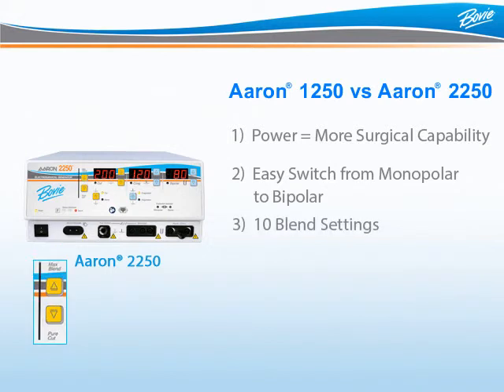Third, the Aaron 2250 offers 10 blend settings so the surgeon can find his perfect blend of cut and hemostasis.